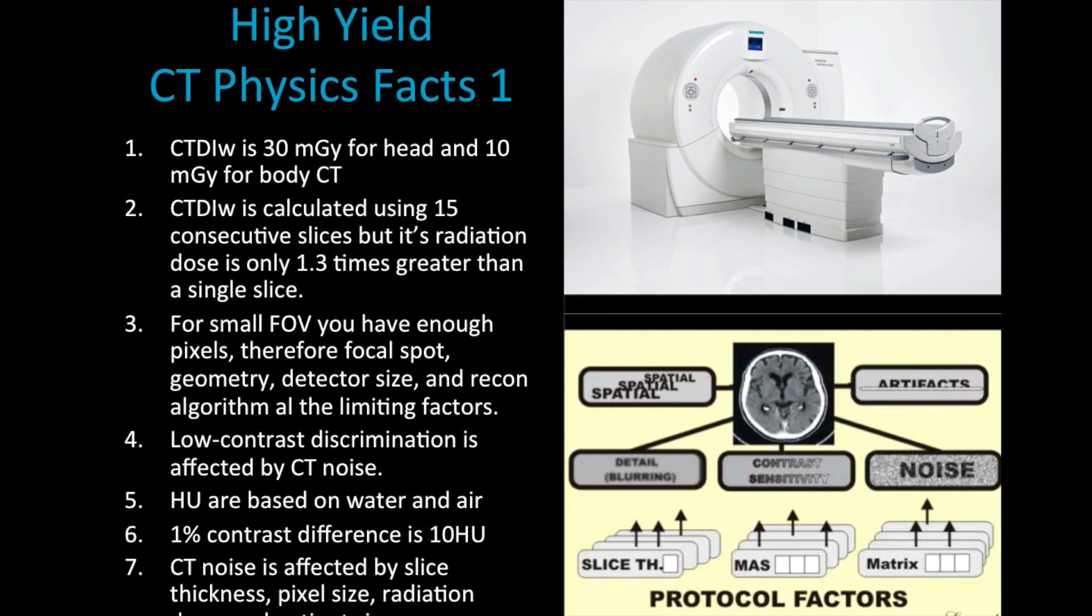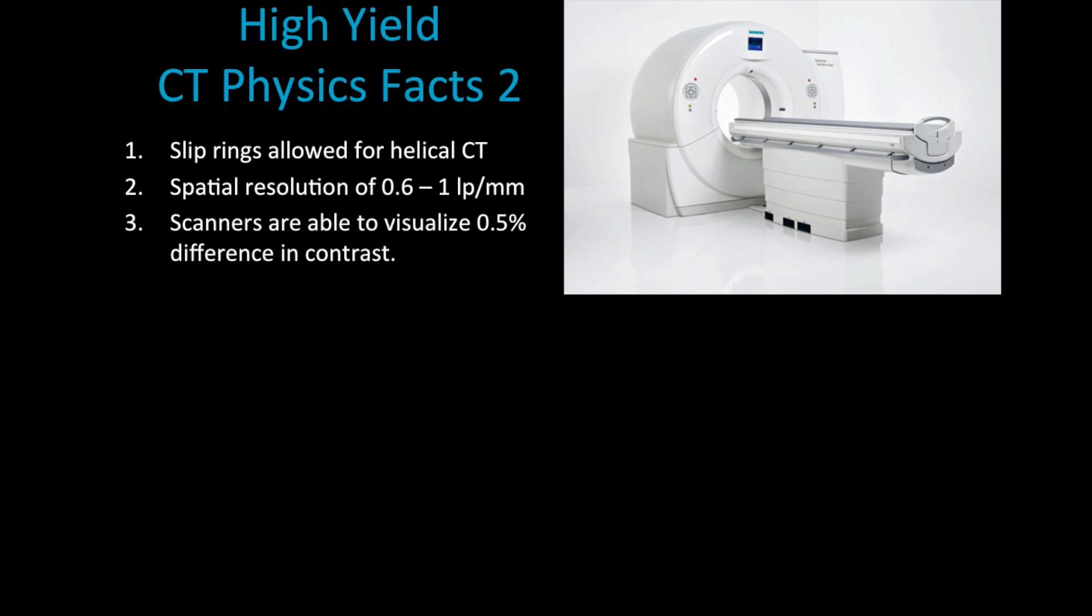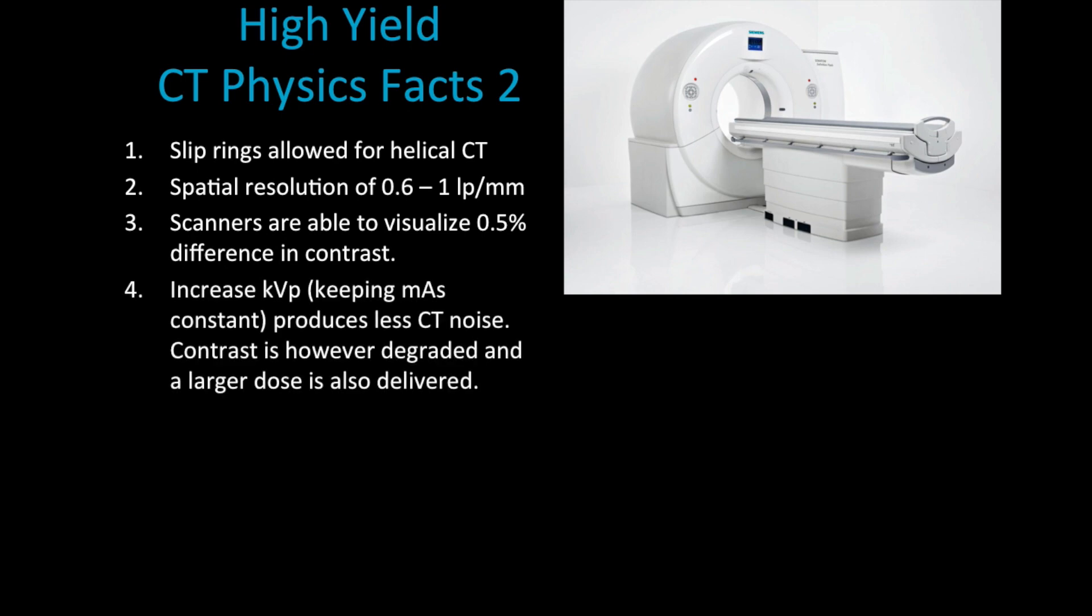Slip rings allowed us to create helical CTs because we removed or eliminated the need of some of the wiring that was required before. The spatial resolution for CT is from 0.6 to one line pairs per millimeter, and this is really low when we compare it to other modalities in radiology. But it shows you that the real importance of CT is in contrast resolution. Scanners are able to visualize 0.5% difference in contrast between two objects.